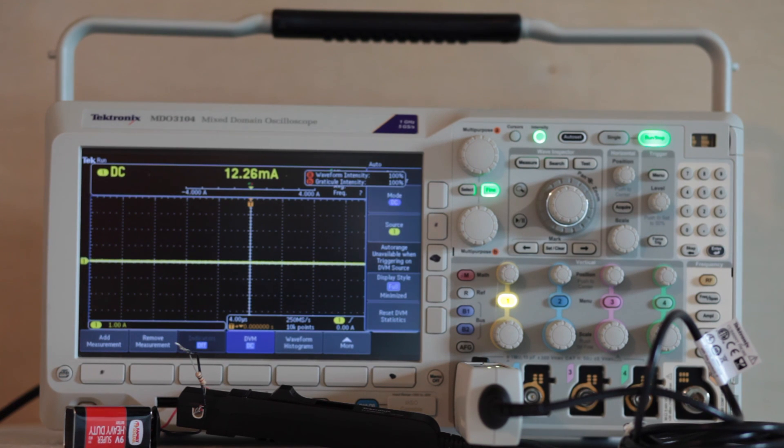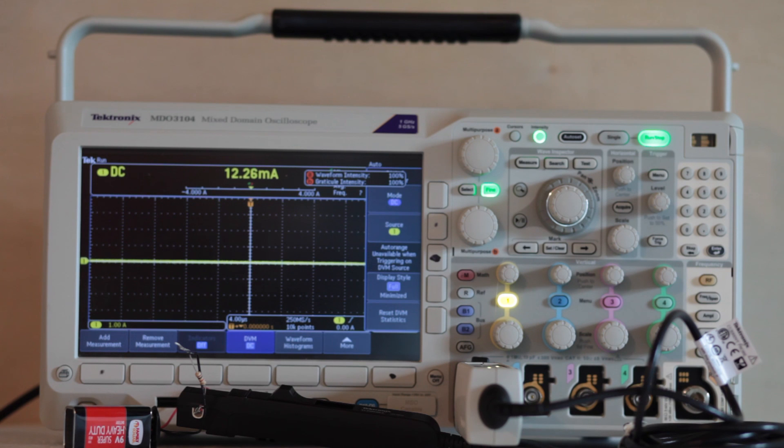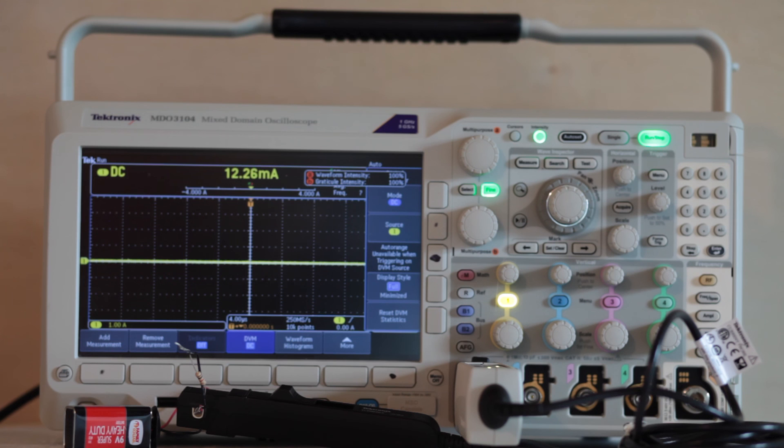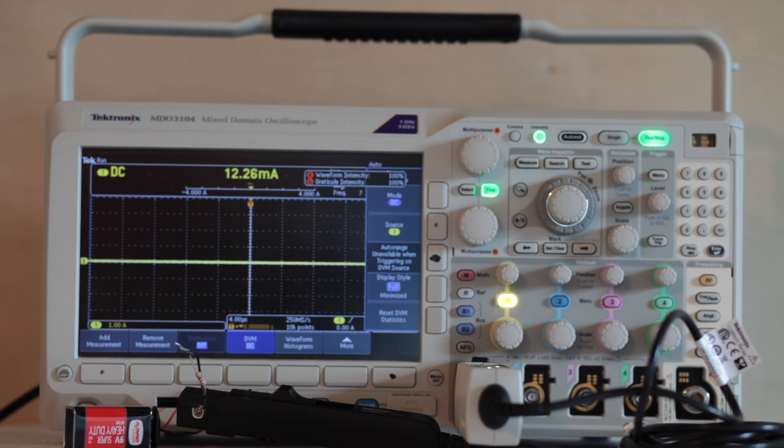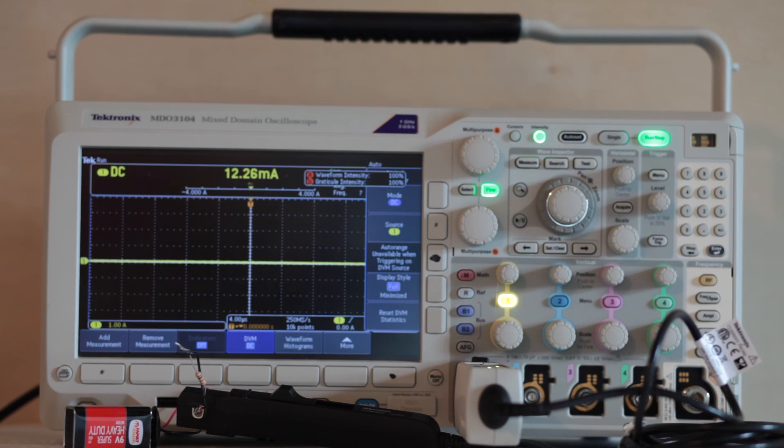To extend the DC current range, you can add offset bucking current through a second conductor, suitably powered and polarized. You can extend the amount of bucking current by wrapping additional turns of the second conductor around the probe so that they pass through the jaws multiple times.